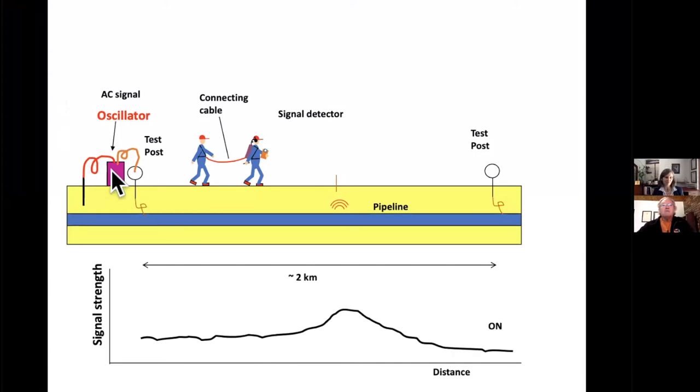In order to measure the gradient you have to have contact, so the original Pearson survey technique used an interesting method. You had two people tethered together by an interconnecting cable, and they would wear conductive boots — that gives you the signal from the ground, and since you're always standing on the ground you don't have to worry about losing contact and getting false indications. The signal generator was a specific AC frequency, matched to the characteristic of the pipe — different frequencies for, say, a bitumen coating versus a fusion bonded epoxy coating.